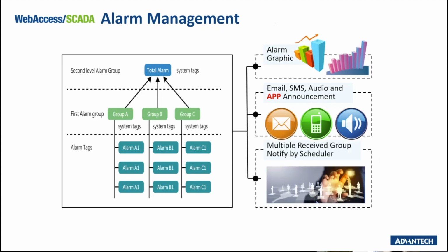Third, the alarm group. The alarm group can be configured in the arrangement that you see on your left, in the diagram. You can define those users under which group and to receive which type of alarm. The user can display the alarm group using the automatically generated alarm group display. An alarm group is typically a processing unit in a multi-process facility. So you can do a breakdown in terms of alerting different operators or different sectors within your organization. So you can do grouping on that portion.